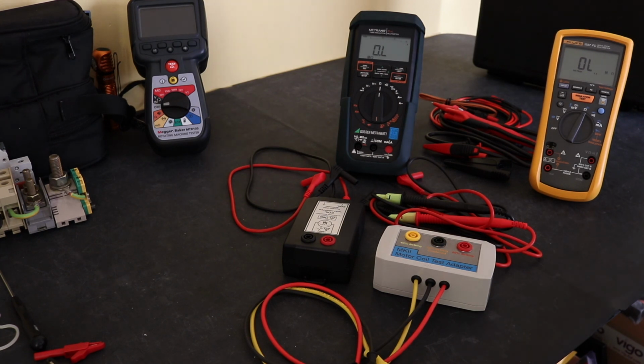The only thing that the MetraHit really brings to you is this inter-turn coil test that is unique to that instrument. I've not seen any other instruments come out with that at this moment in time, but as I said, it is unstable and I've had to develop my own adapter in order to give it some stability, which has improved it but not solved it 100%. So unless you have a specific need for testing inter-turn faults, I would plump for this 1587 every single time.